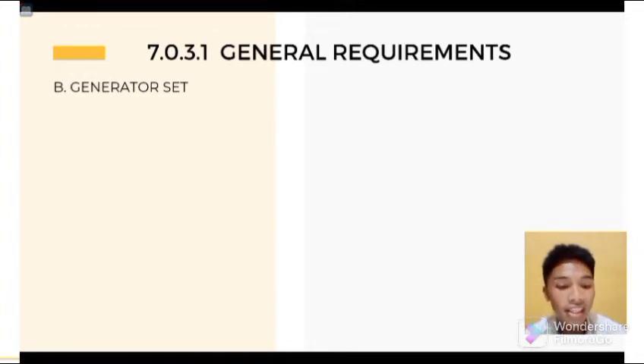Number 5, auxiliary power supply. Generator sets that require more than 10 seconds to develop power shall be permitted if an auxiliary power supply energizes the emergency system until the generator can pick up the load. Number 6, outdoor generator sets. When an outdoor housed generator set is equipped with a readily accessible disconnecting means located within sight of the building or structure supplied, an additional disconnecting means shall not be required where ungrounded conductors serve or pass through the building or structure.